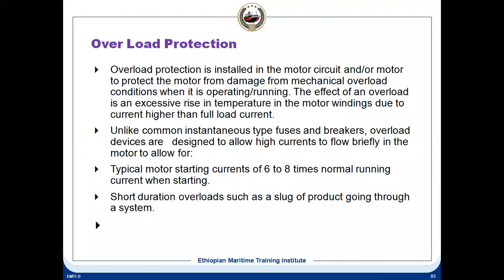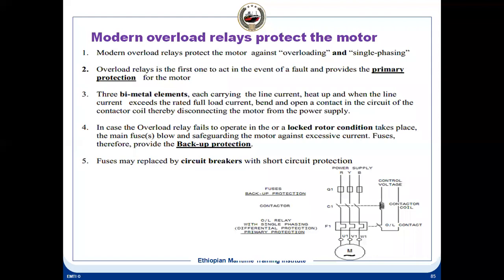The effect of the overload is basically an excessive rise in temperature in the motor winding due to current higher than the full load current. Unlike common instantaneous type fuses and breakers, overload devices are designed to allow high currents to flow briefly in the motor, to allow for the typical starting current of up to 6 to 8 times normal running current when starting. So motor overload relays protect the motor against overloading and single phasing.